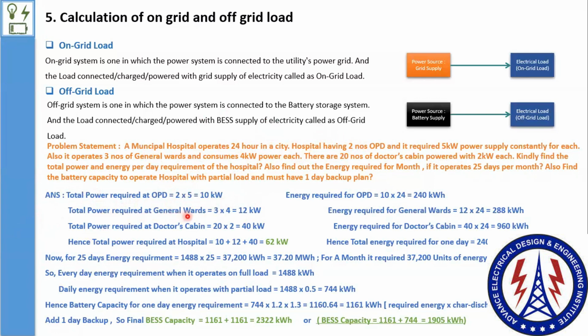Power requirement for the general wards: 3 general wards, each consuming 4 kilowatts, so 12 kilowatt total for general wards. For the doctor's cabin, there are 20 cabins, each requiring 2 kilowatt, so total 40 kilowatt. Summing all three, total power requirement at the hospital is 10 plus 12 plus 40, which is 62 kilowatt, the peak load I am considering.